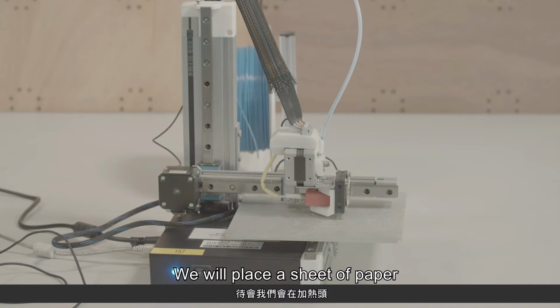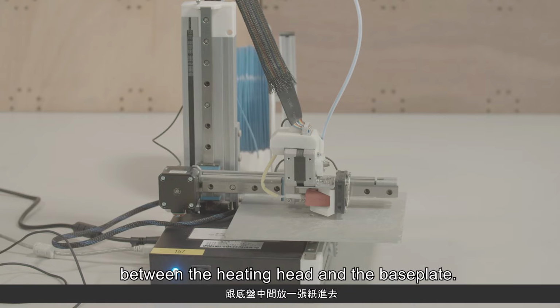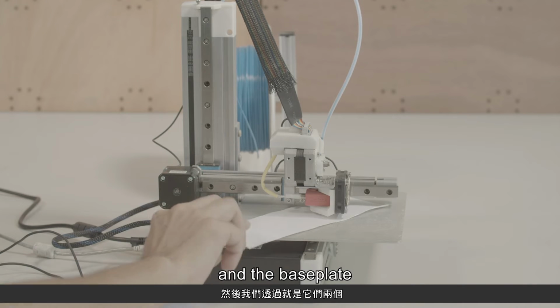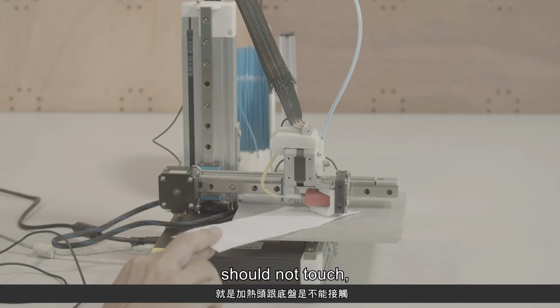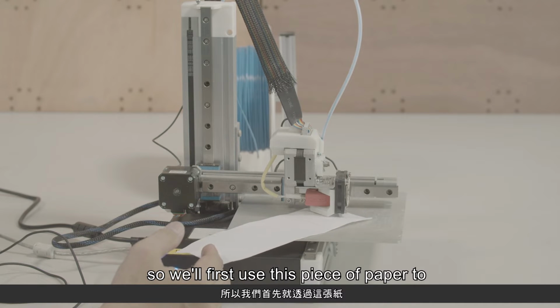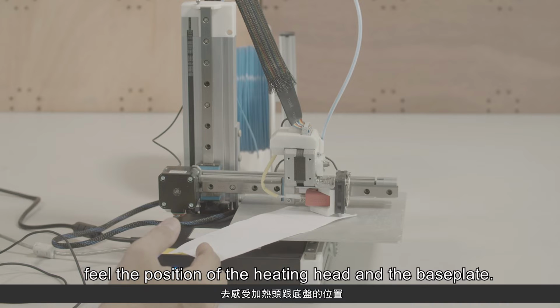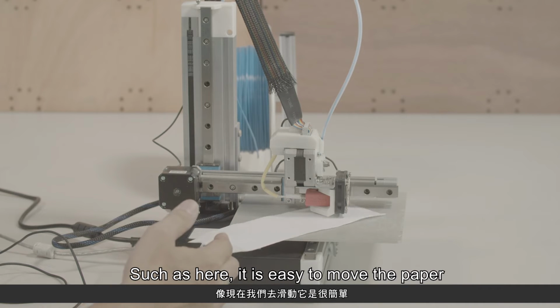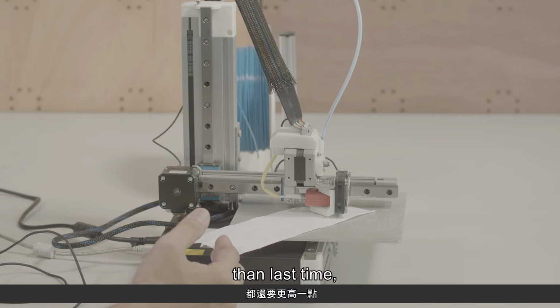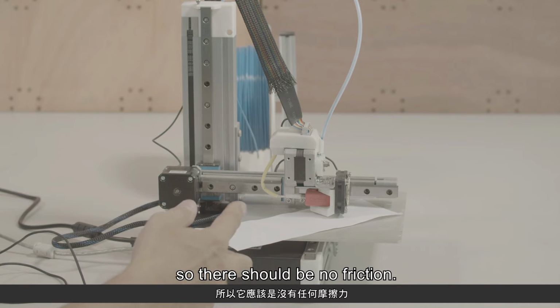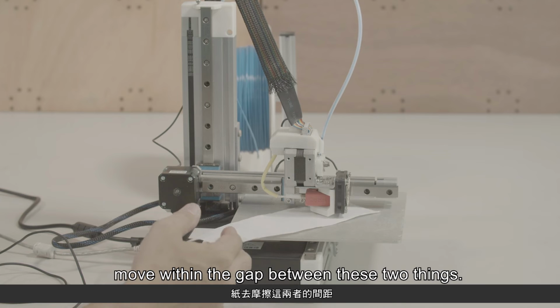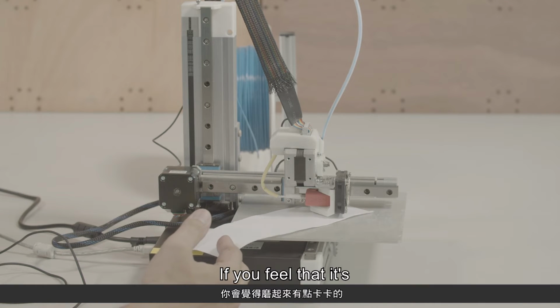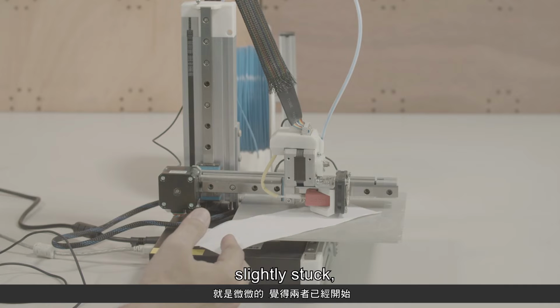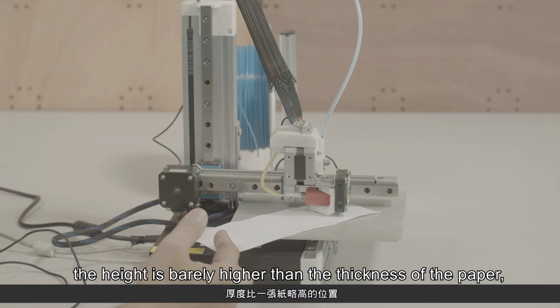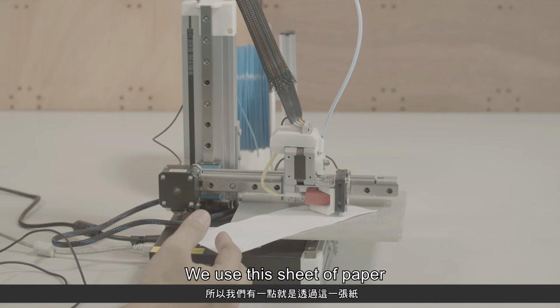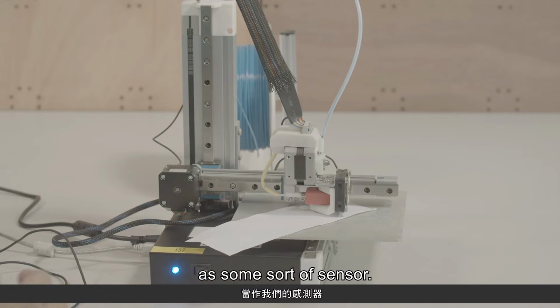We will place a sheet of paper between the heating head and the base plate. The heating head and the base plate should not touch. So we'll first use this piece of paper to feel the position of the heating head and the base plate. Such as here, it is easy to move the paper because the height is set higher than last time, so there should be no friction. We'll use this piece of paper to move within the gap between these two things. If you feel that it's slightly stuck, the height is barely higher than the thickness of the paper, then that's the position we need to measure.